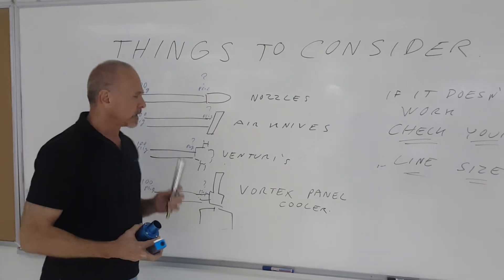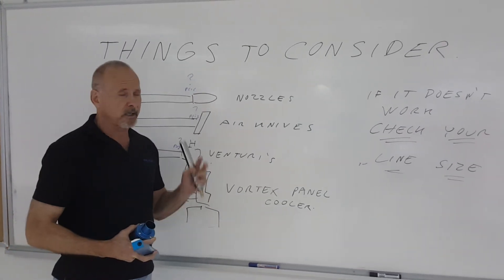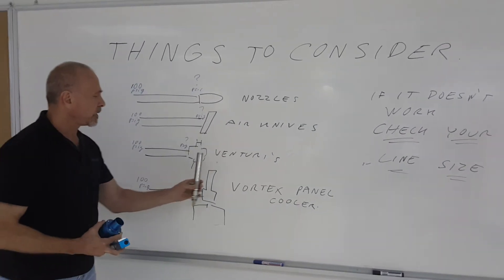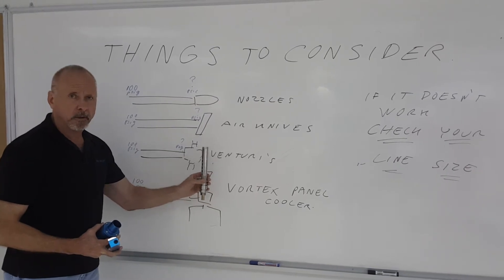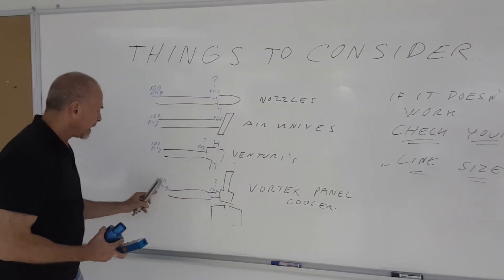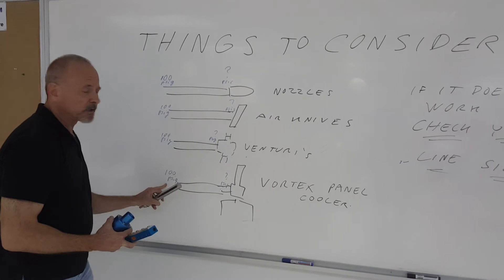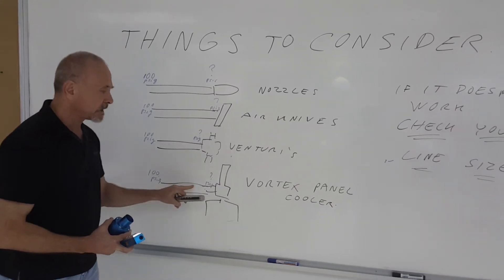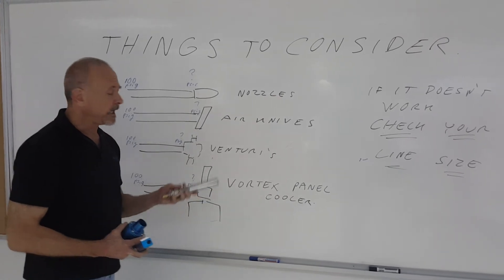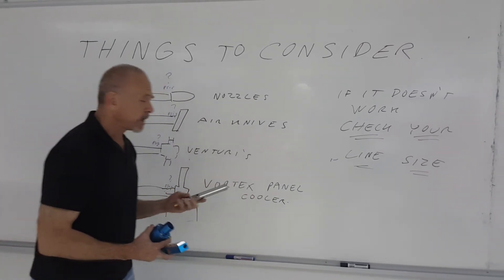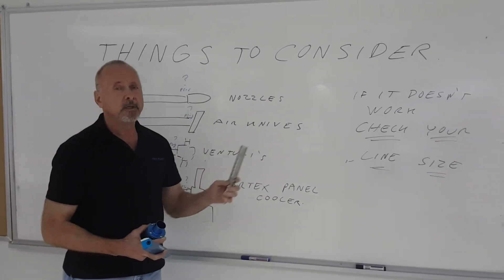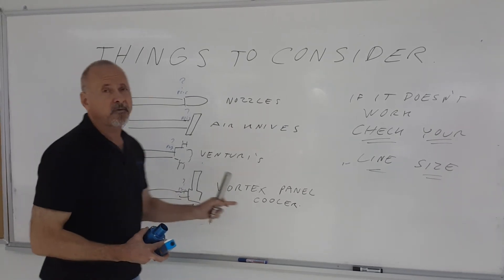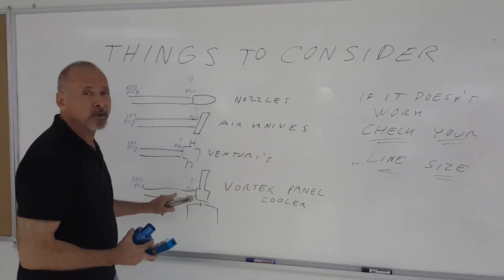And finally, people don't even notice most of the time unless there is a problem in cooling - it's not cooling enough - is the supply line to a vortex panel cooler. Again, upstream it could be 100 pounds per square inch, but depending on the size of the cooler, you better watch the size of your supply line. I have seen eight millimeter supply lines trying to supply 40 CFM to a cooler that's maybe 10 feet long. It's not going to work - you're going to have a tremendous pressure loss.